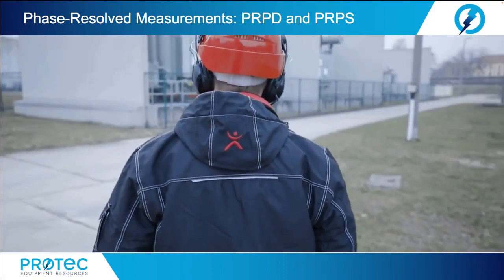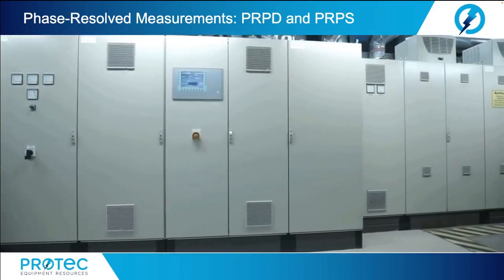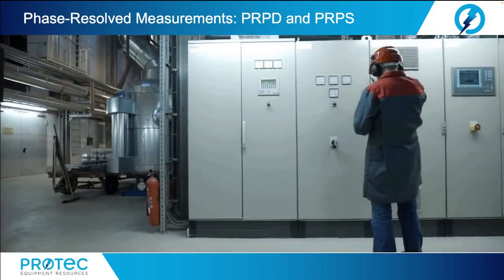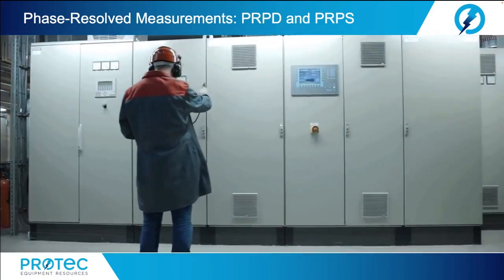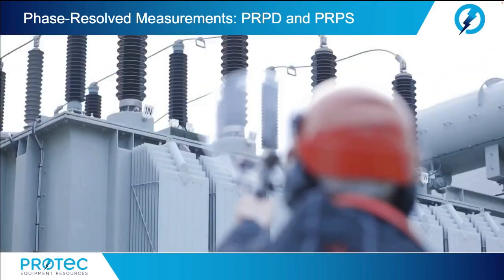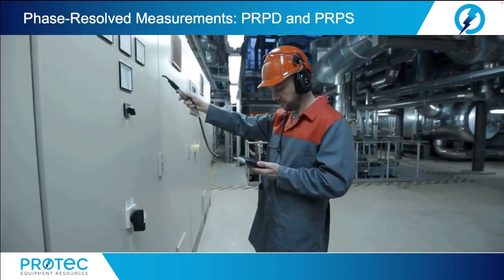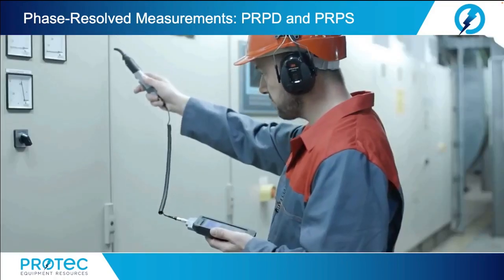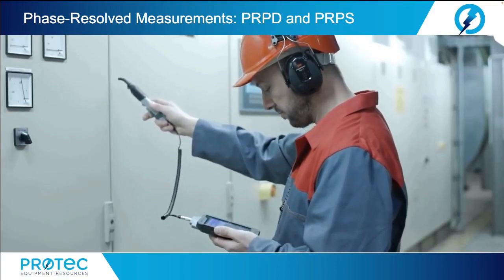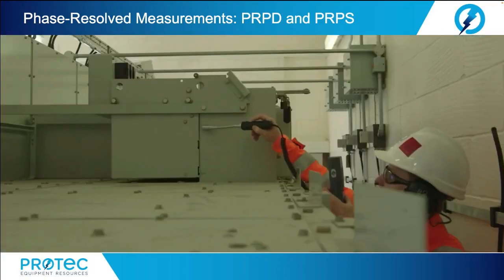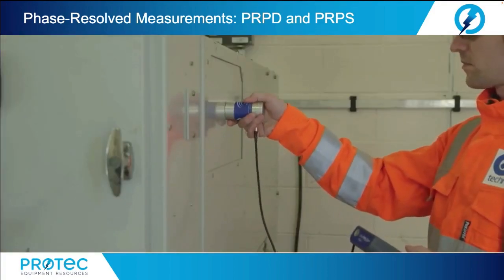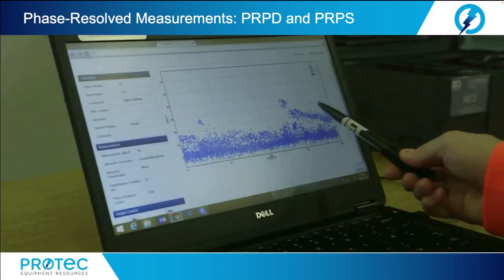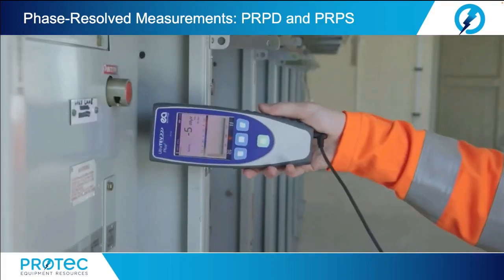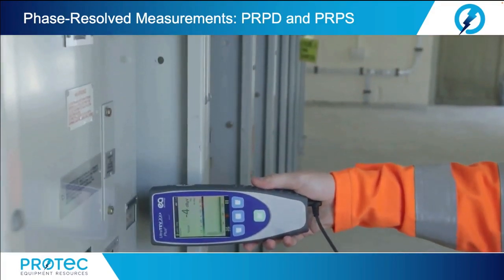Now, when using UHF, HFCT, or ultrasonic sensors, we use a concept called phase-resolved analysis. Consider the sensor that you're using. It has a bandwidth that spans portions of the radio frequency spectrum or the ultrasonic spectrum. There are all kinds of other signals and other energy in that bandwidth that has nothing to do with partial discharge. It's what we call noise. For example, telecommunication signals can be an example of noise.